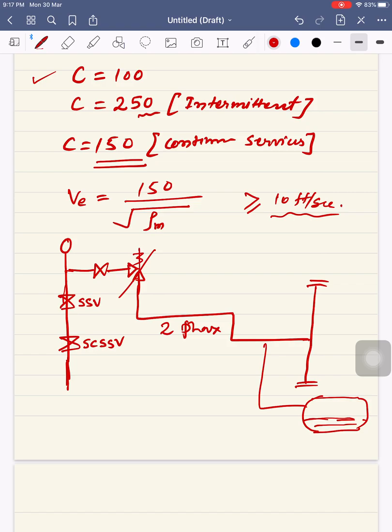That ensures the slip ratio is one between gas and liquid. If velocity is less than 10 feet per second, that may cause slugging in the separator. Slugging means an abrupt bunch of liquid coming in a certain frequency into the slug catcher or separator.